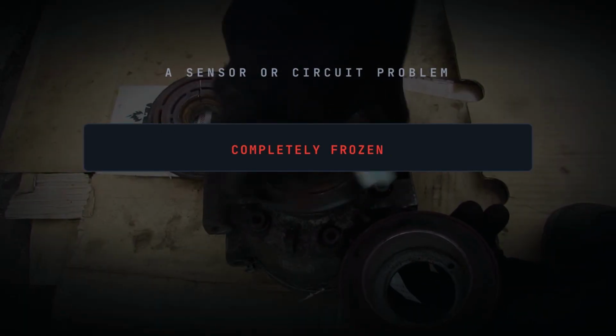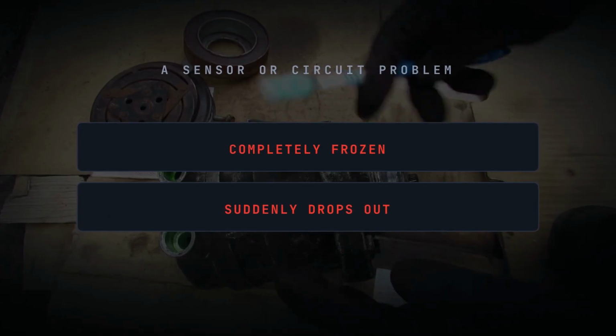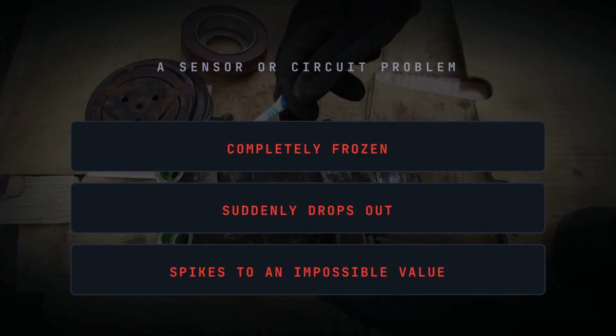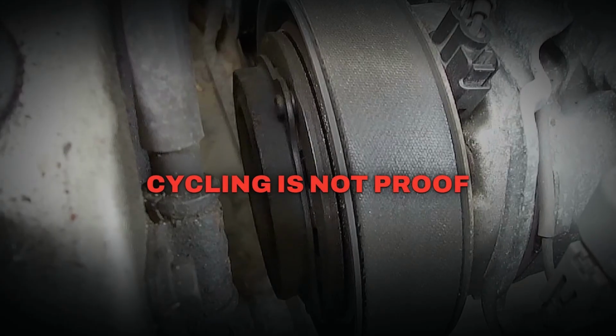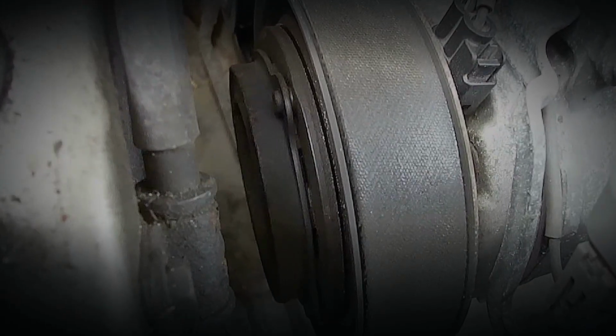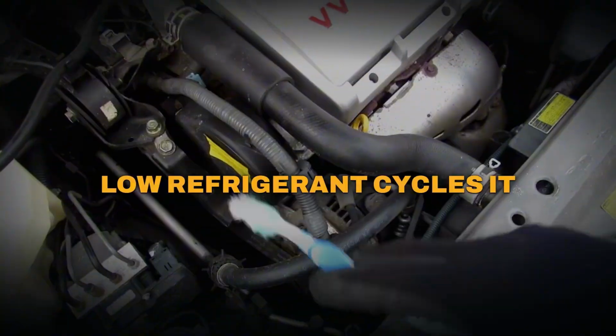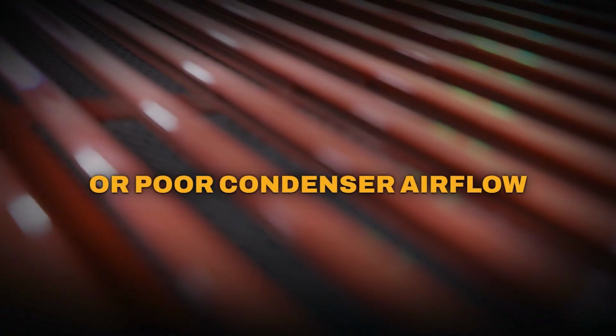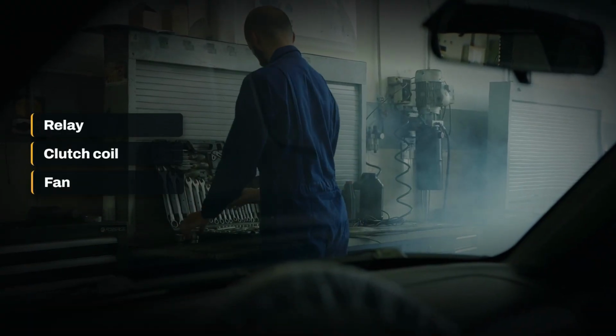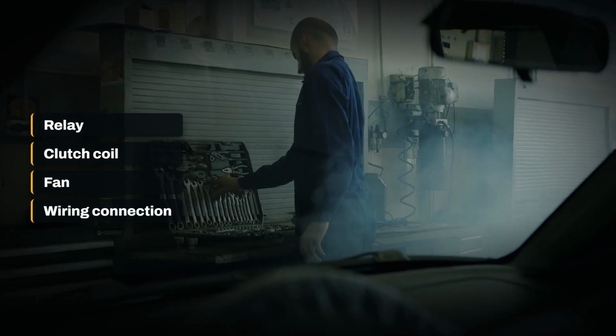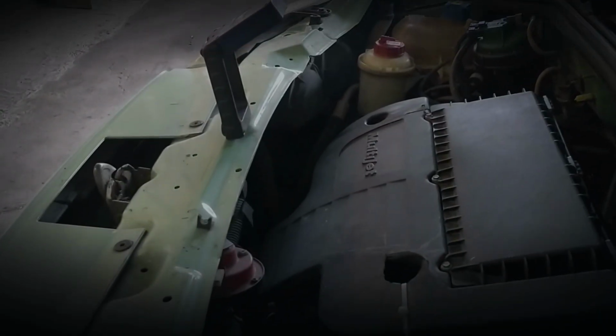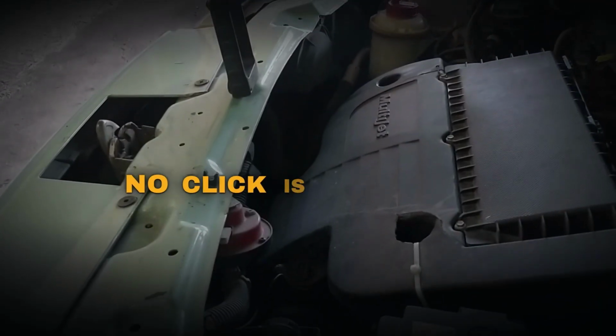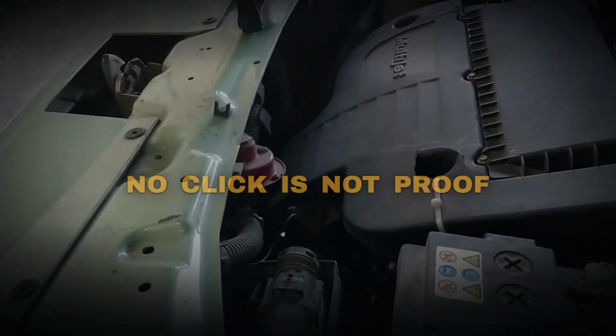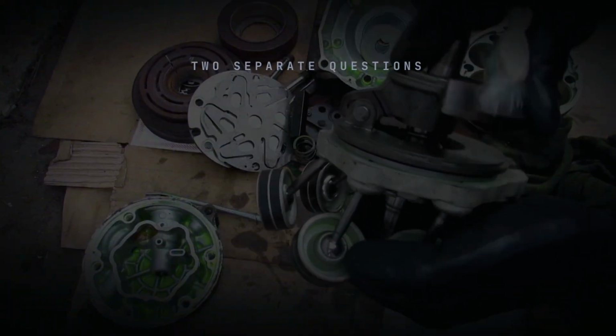A reading that stays completely frozen, suddenly drops out, or spikes to an impossible value may indicate a sensor or circuit problem. But rapid clutch cycling does not prove the pressure sensor is bad. Low refrigerant can make the protection system cycle the compressor. High pressure caused by poor condenser airflow can also change compressor operation. A failing relay, clutch coil, fan, or wiring connection can produce similar symptoms. Some modern compressors control output without traditional clutch cycling, so the absence of a click does not automatically indicate a failure. Use the data to answer two separate questions.